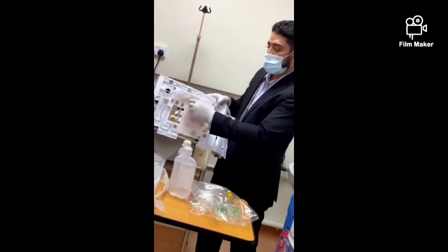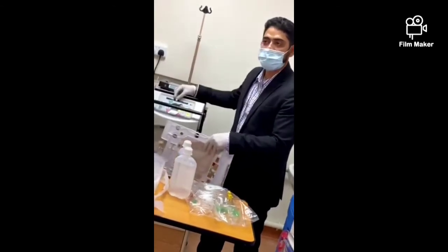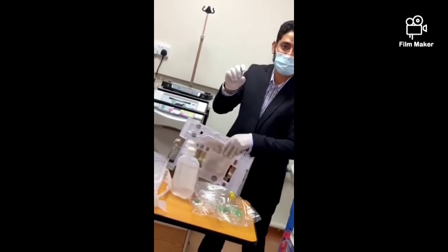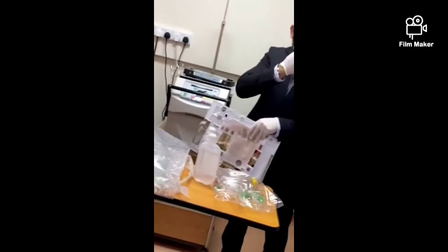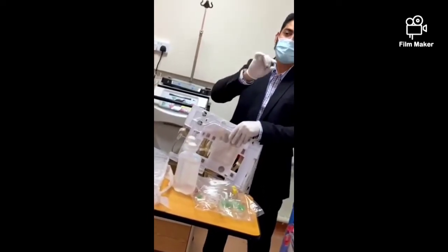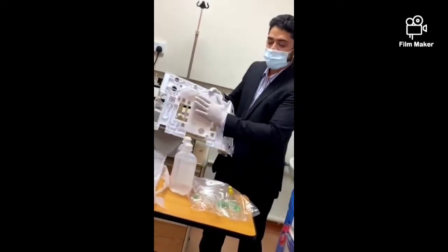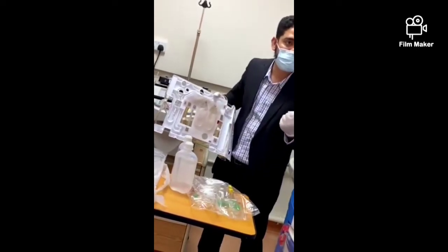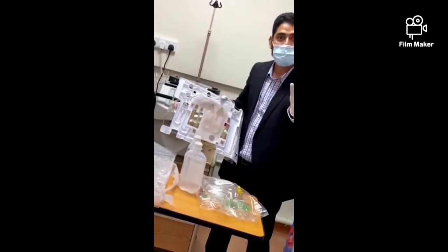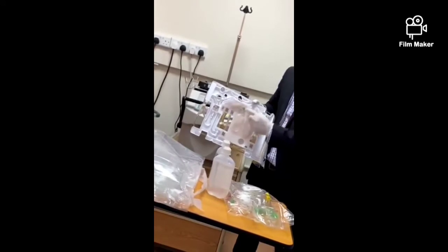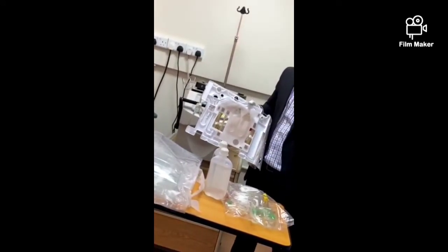So why is this so? Because there is one, number 2, that will come. This means volumetric check. Every 1 hour we have the volumetric check. We made already 1 hour. So this volumetric check is checking whether it is accurately removing or not. Yani, even 10 ml you cannot remove extra. It is checking that. That is for the safety of the patient. That is the number 2.